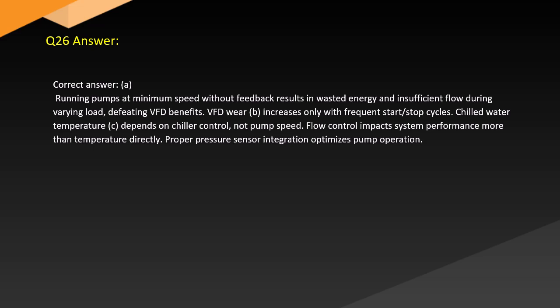Answer. Correct answer. A. Running pumps at minimum speed without feedback results in wasted energy and insufficient flow during varying load, defeating VFD benefits. VFD wear, B, increases only with frequent start-stop cycles. Chilled water temperature, C, depends on chiller control, not pump speed. Flow control impacts system performance more than temperature directly. Proper pressure sensor integration optimizes pump operation.